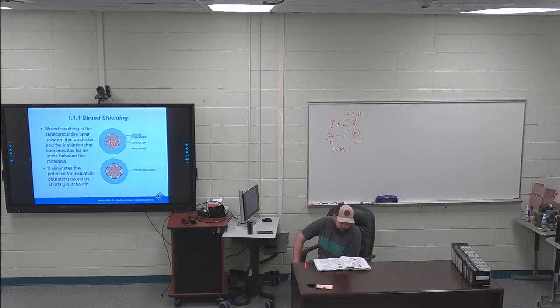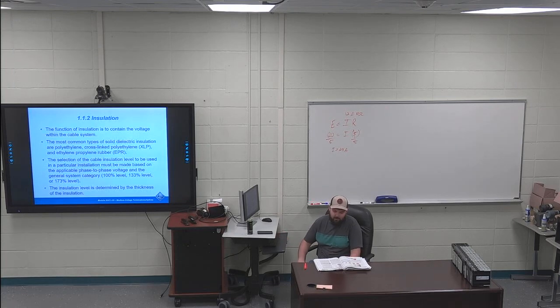Insulation, 112. You're going to test insulation at different levels in the factory. So they got the 100% level, 133%, and the 173% level. I've got the 173% level in 112 highlighted. Cables in this category should be applied on systems where the time required to de-energize a grounded section is indefinite. Their use is also recommended for resonant grounded systems. Consult the manufacturer for insulation thickness requirement. So those are tested up to 175%.